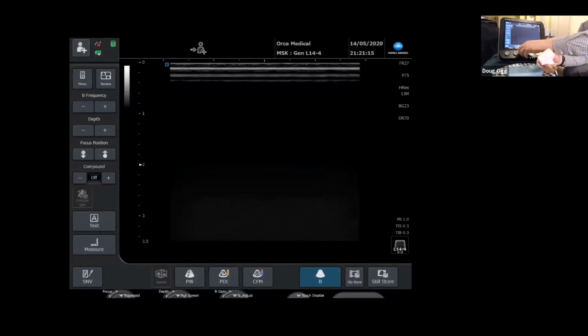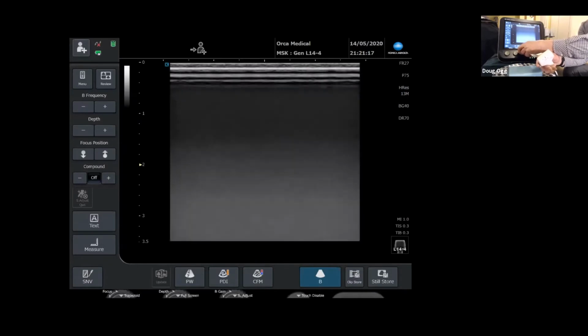probe. Now I'm going to need to turn up the gain on the machine for you to see this, and make sure that it's got some gel on it. I don't know if you can see that very well. Let me just put it in the right place. As I run this across, can you see that line of contact move across? Now, if there was a dropout, a broken transducer crystal, at a consistent point the line would completely disappear, and then it would come back.